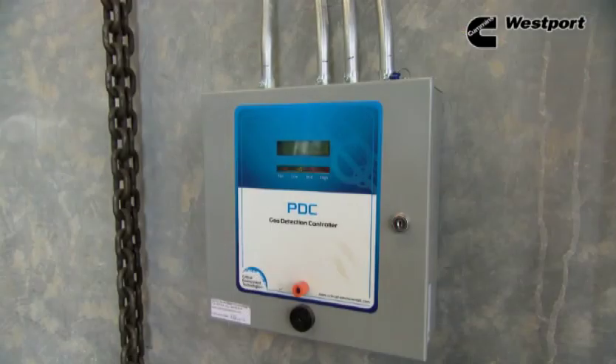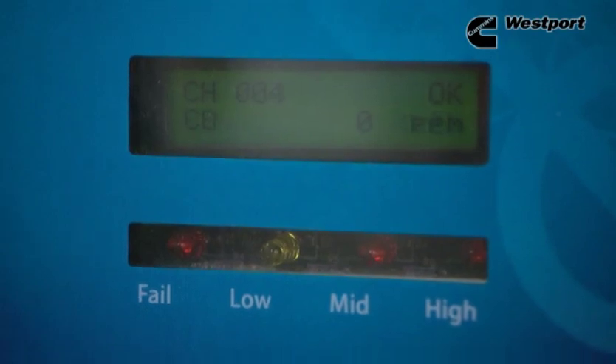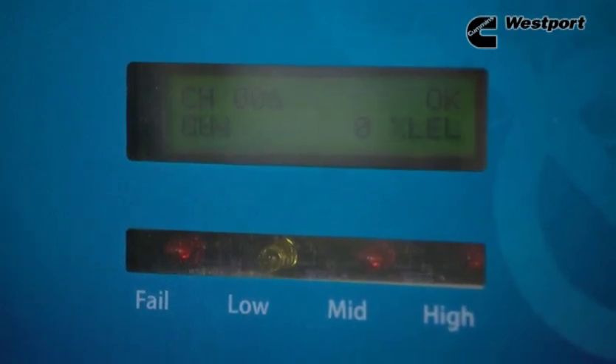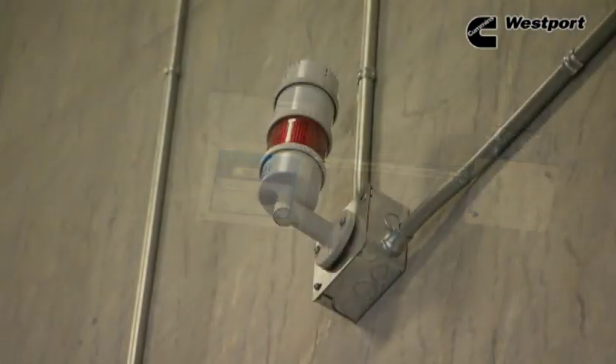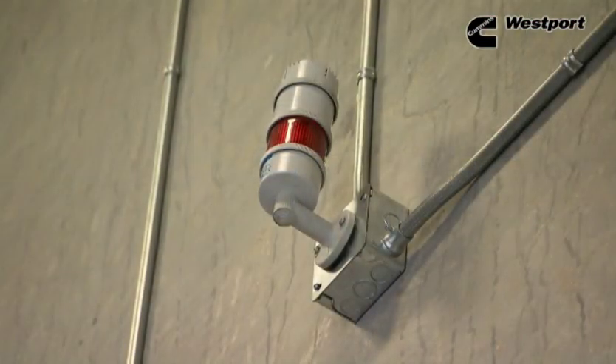So primarily you'll have an alarm panel tied into a methane detection system. The methane detection system will then detect gas at the appropriate level, probably about 10% of the lower explosive limit of a gas leak, and that gas would be accumulating in the top part of the building. So when you're talking about how everything works together in the event of a leak, a shop like this, for instance, will have an alarm panel. The alarm panel is tied into the methane detection system.